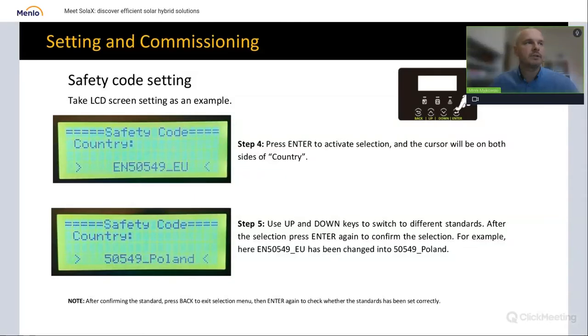If it's not correct, you just have to edit this, press enter to activate the selection. Then those two arrows on the side will appear, and you can use up and down to choose the appropriate safety code, confirming with enter again. My suggestion is when you go back, go in again and check on the main page that what you just chose is set, so you'll be sure all the grid standard settings are in place.